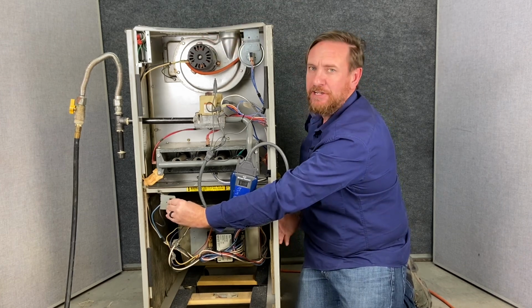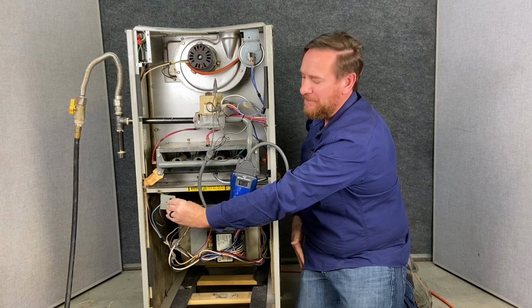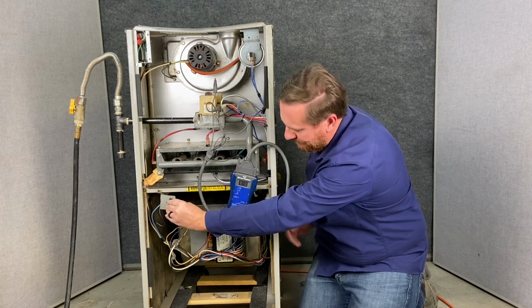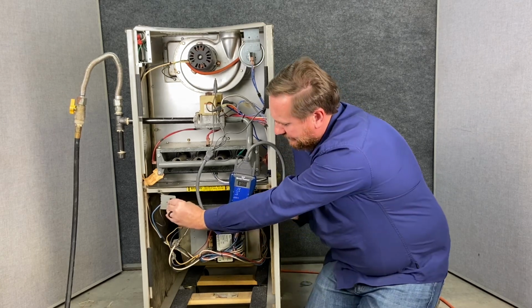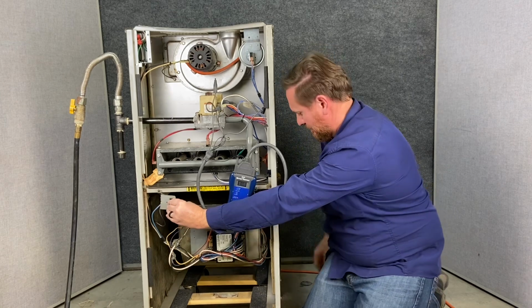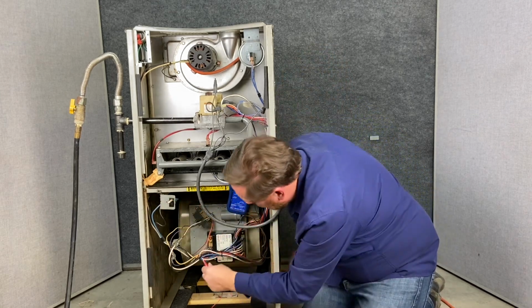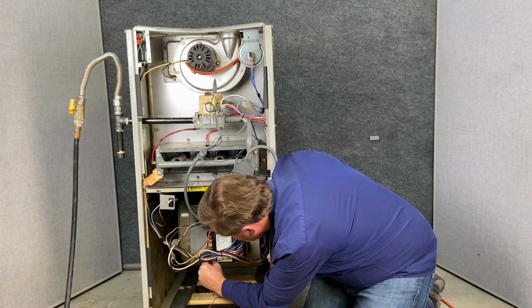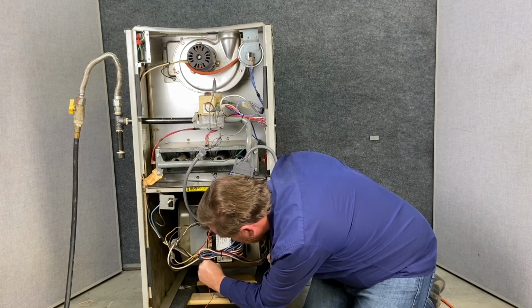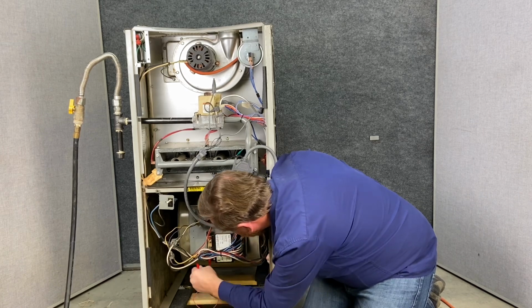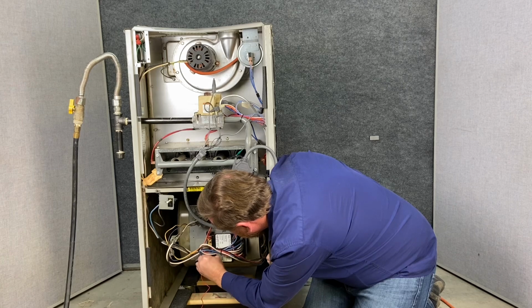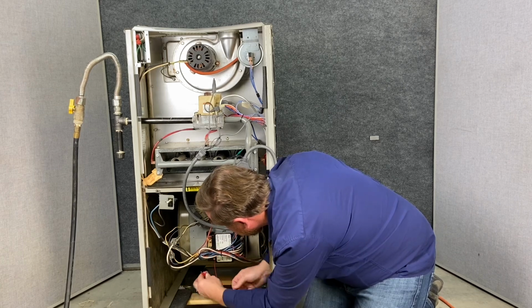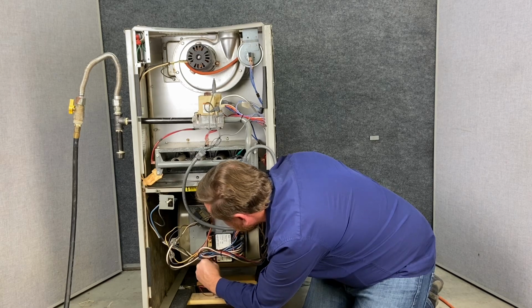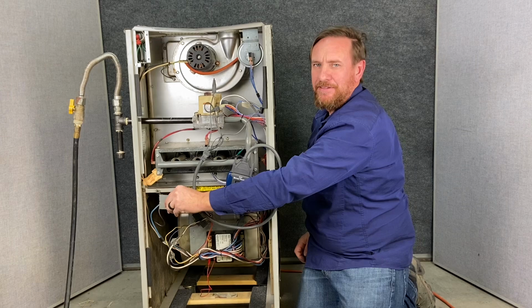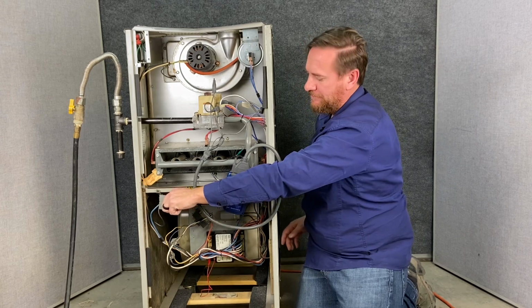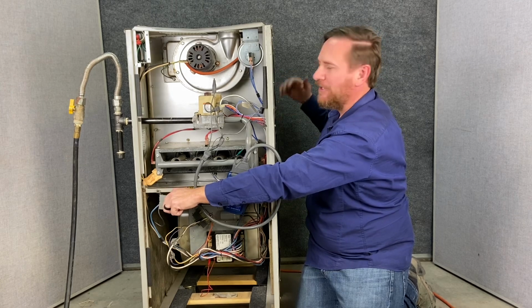And we do have some kind of an issue because the blower in this system never did cut on. So I'm going to manually jump that out to cool this heat exchanger off for safety. And we can see that all of our lights ended, except we still have 24 volt power and polarity. So I'm going to turn the fan to the on position, connecting R and G. Now when I energize my door safety switch, our fan motor itself should come on, and now I'm moving air across my heat exchanger, cooling it down.